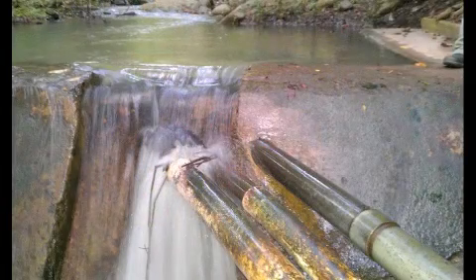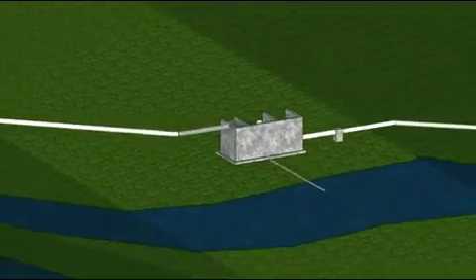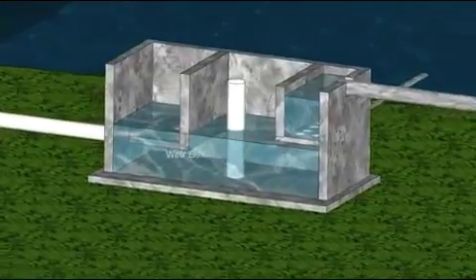From the reservoir, the water flows through the 4-inch piping down into the weir box, 80 meters down the way. The weir box is intended to slow flow and remove sedimentation, but it currently does neither. Therefore, the water that currently flows to the distribution tank is still turbid and sediment-filled.